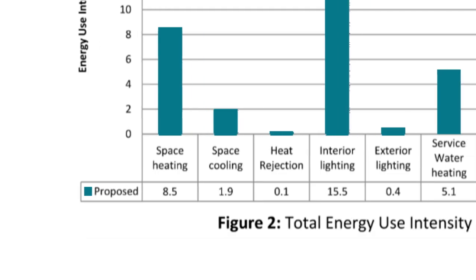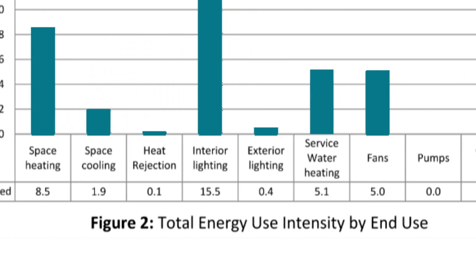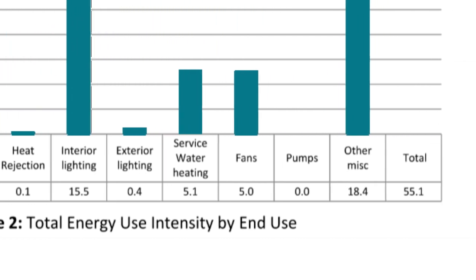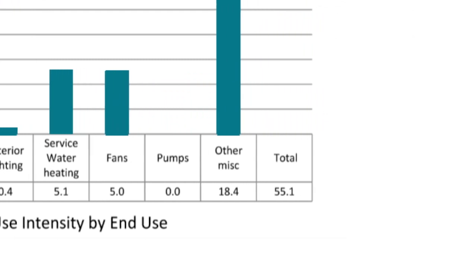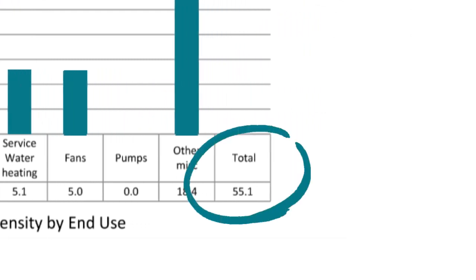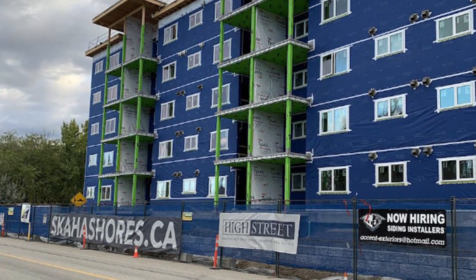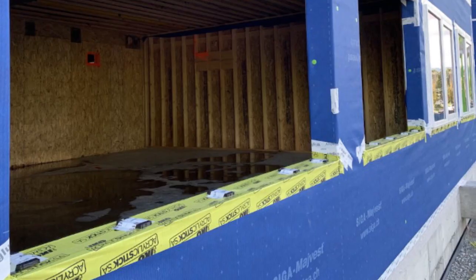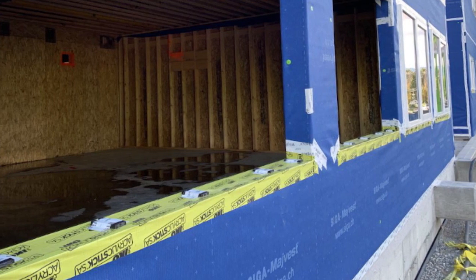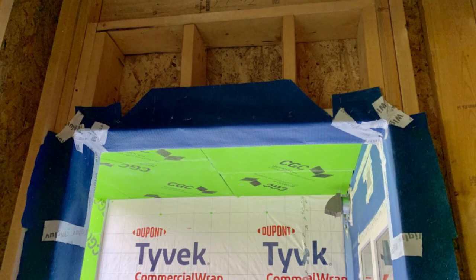This design practice aligned well with the intention of the BC Energy Step Code, allowing for fairly seamless transition between NECB standards and Step Code. Performance-based design has really brought the building energy use incrementally down from total energy use intensities, or TEUIs, of 120 kilowatt hours per meter squared to 55 kilowatt hours per meter squared over the course of 2 years. Around the same time, High Street started infiltration or air tightness benchmarking, and since then have taken those benchmarks and assigned performance criteria for all future buildings.